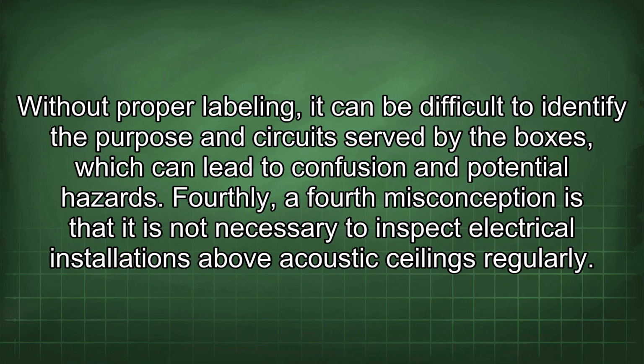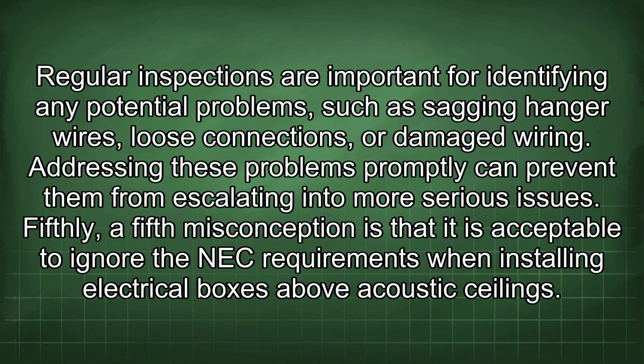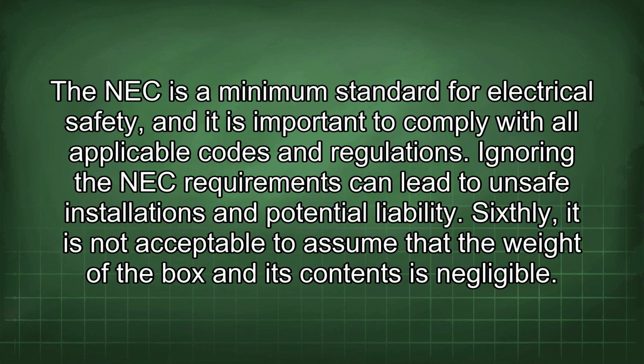Fourthly, a fourth misconception is that it is not necessary to inspect electrical installations above acoustic ceilings regularly. Regular inspections are important for identifying any potential problems such as sagging hanger wires, loose connections, or damaged wiring. Addressing these problems promptly can prevent them from escalating into more serious issues. Fifthly, a fifth misconception is that it is acceptable to ignore the NEC requirements when installing electrical boxes above acoustic ceilings. The NEC is a minimum standard for electrical safety, and it is important to comply with all applicable codes and regulations. Ignoring the NEC requirements can lead to unsafe installations and potential liability.